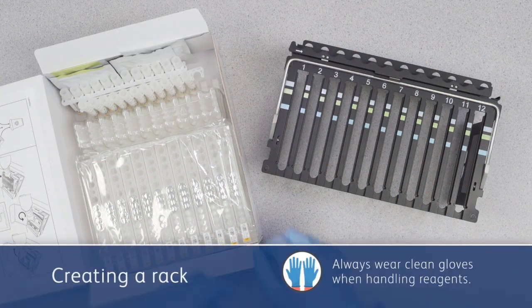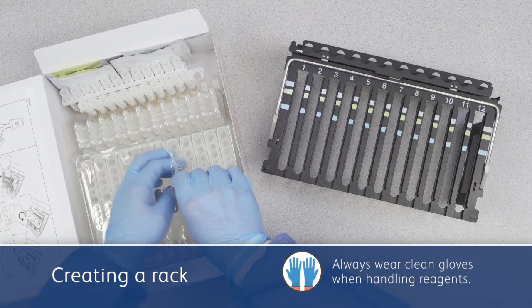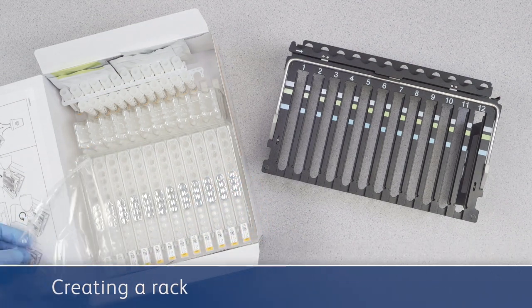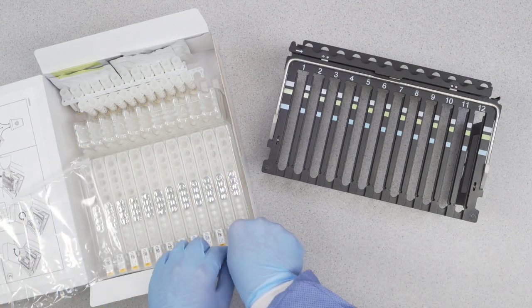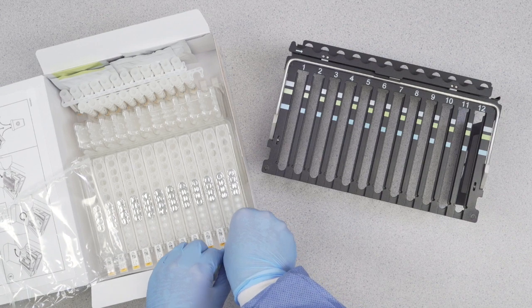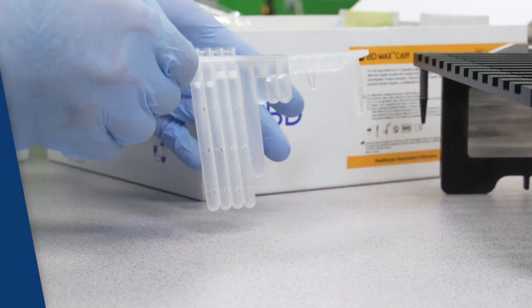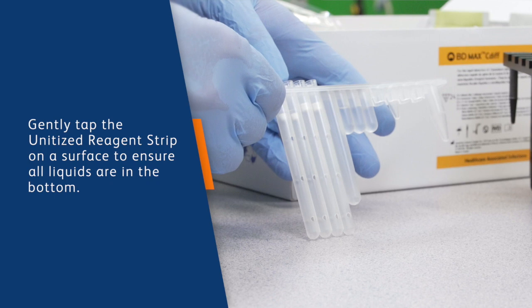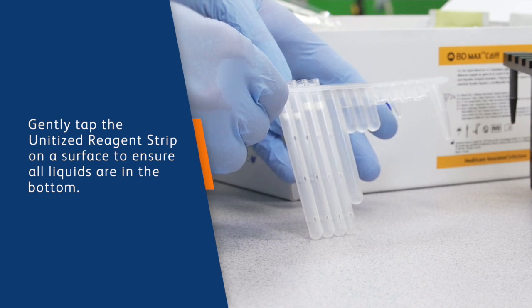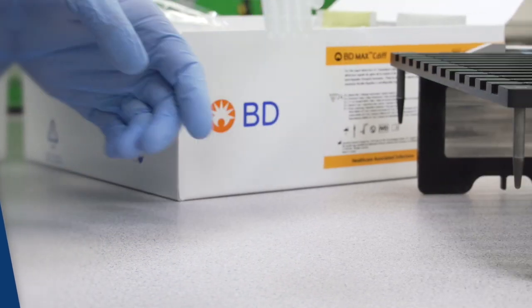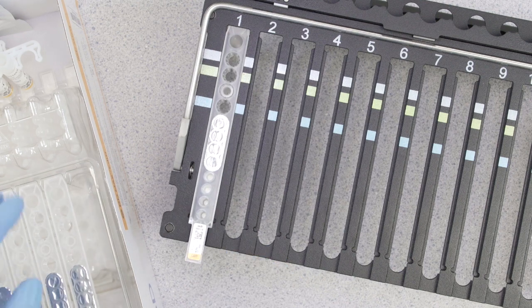When ready to use, peel off the top plastic film and leave the box inside. Remove a unitized reagent strip by holding the tab and lifting it straight out of the box. Gently tap the unitized reagent strip on the table or surface to ensure all the liquids are in the bottom of the tubes. Then, place it into the rack with the barcode facing you.